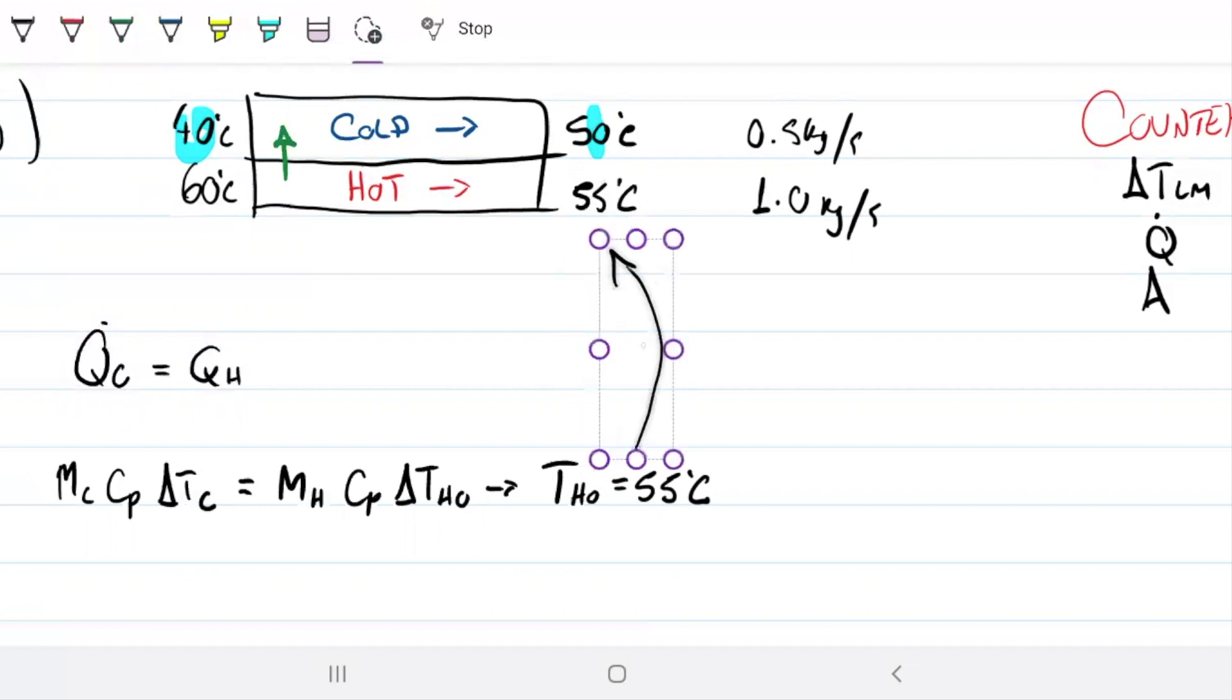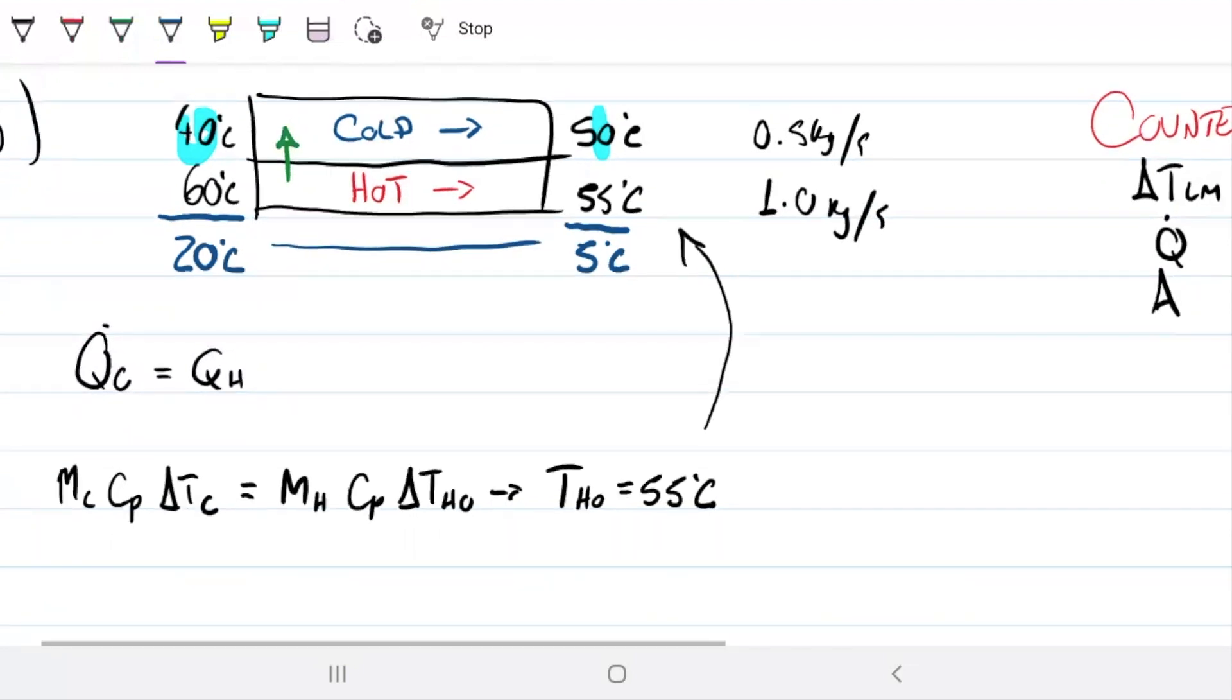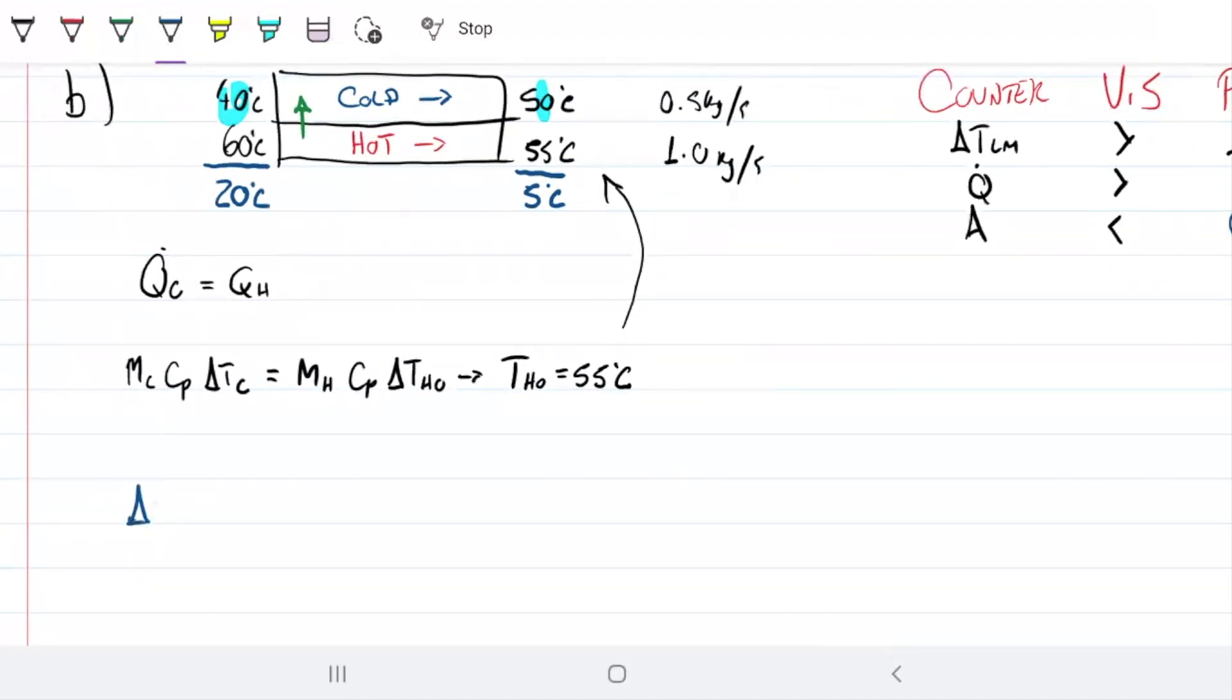However, what does change now is our delta T's, because on this side here we have 20, which is a big delta T in comparison to the others, but over here we only have 5. So our log mean now is going to be somewhere between 5 and 20. Our delta T log mean is (20 minus 5) divided by the natural log of 20 over 5. This turns out to be 10.82. Remember what it was for the previous one, it was 12.33, so note how nothing changed between the two except the delta T natural log mean.